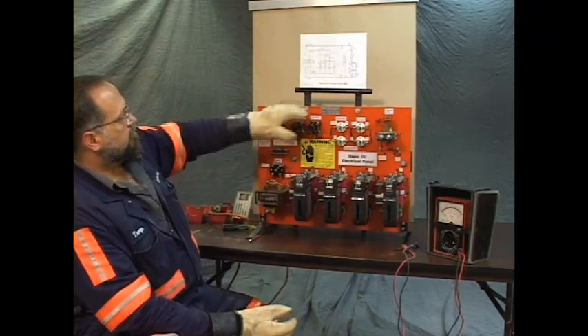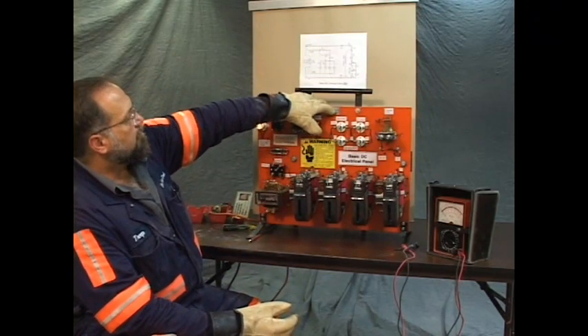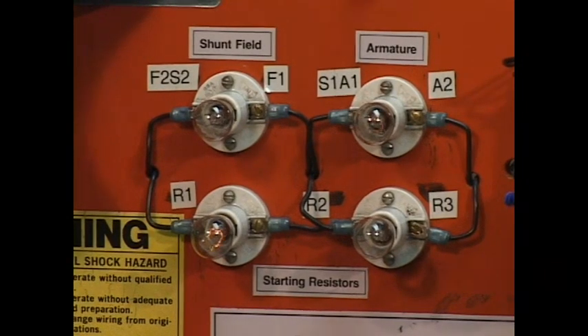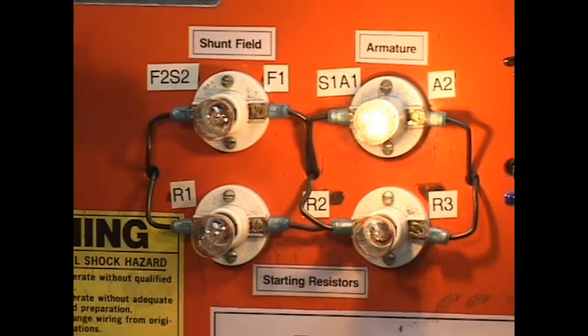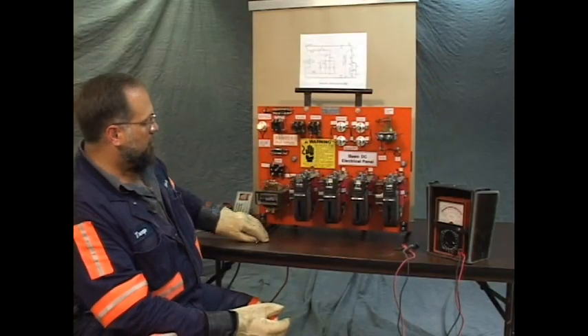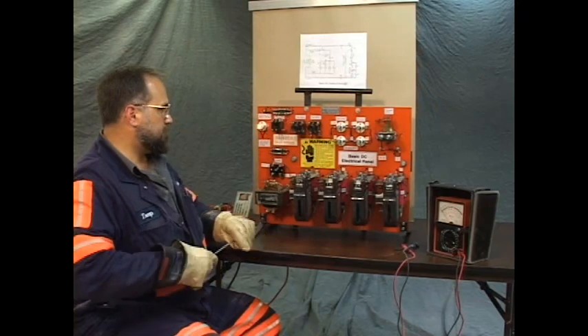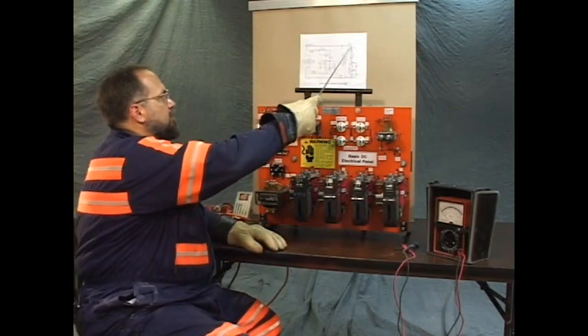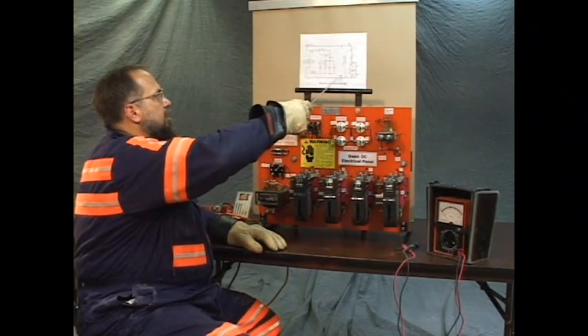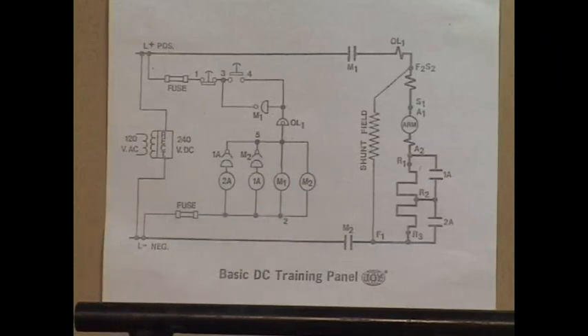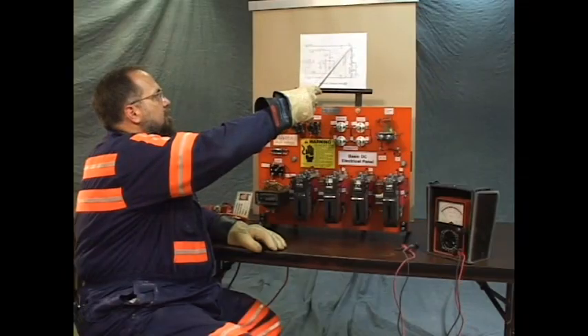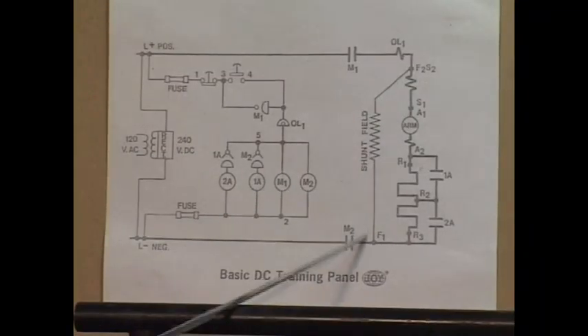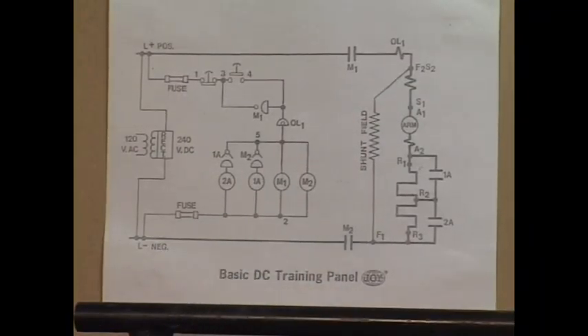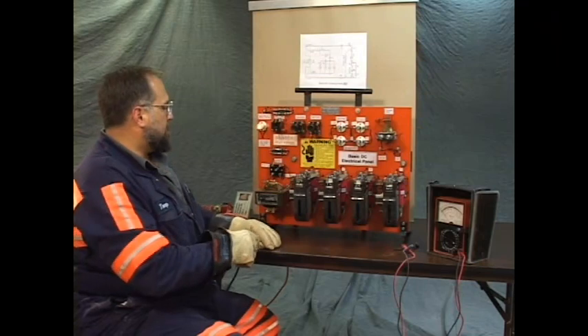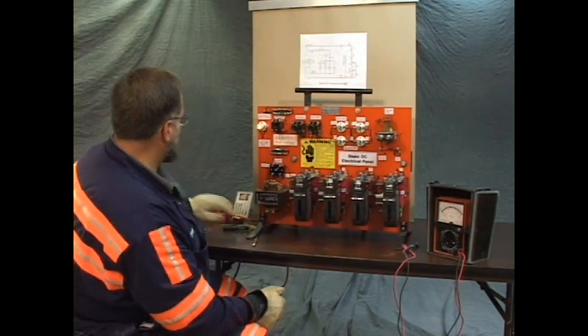So, our problem is with the shunt field branch. Looking at the drawing, this portion of the panel is operating correctly. The control portion of the panel is operating correctly. The only part that's not operating is from here to here, this particular branch. So let's take our power off, lock and tag.